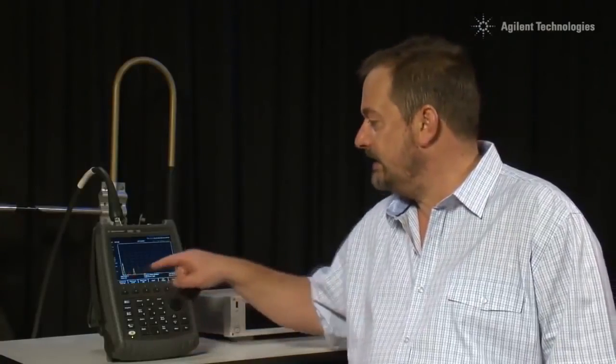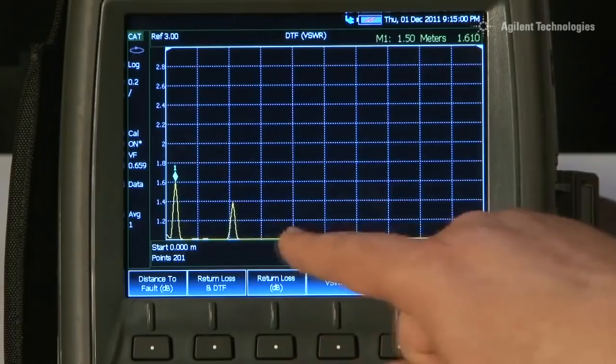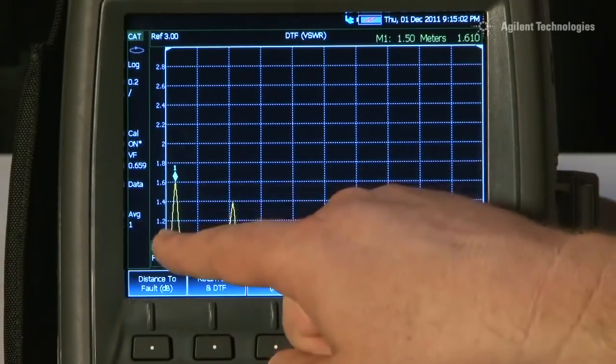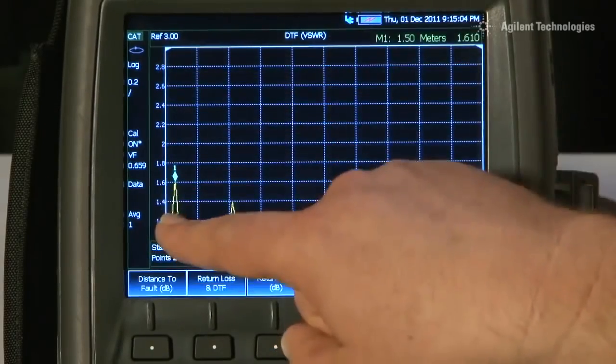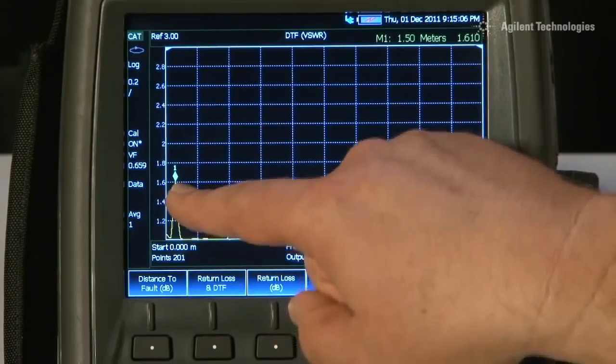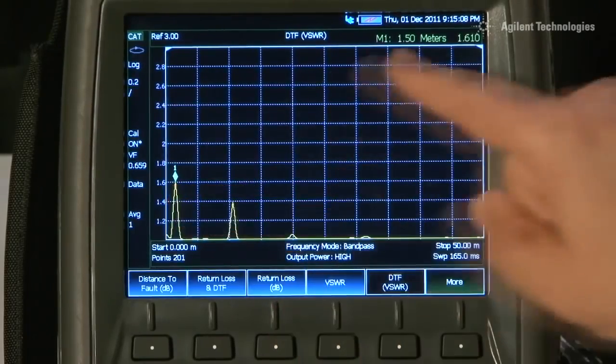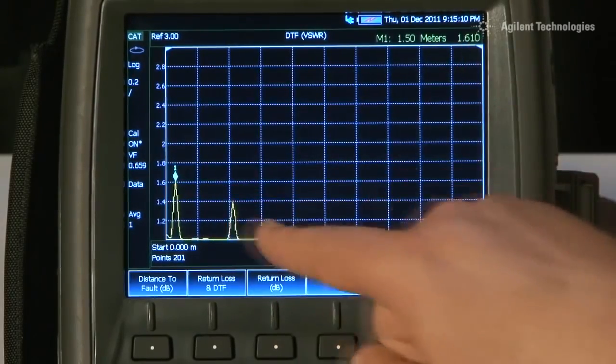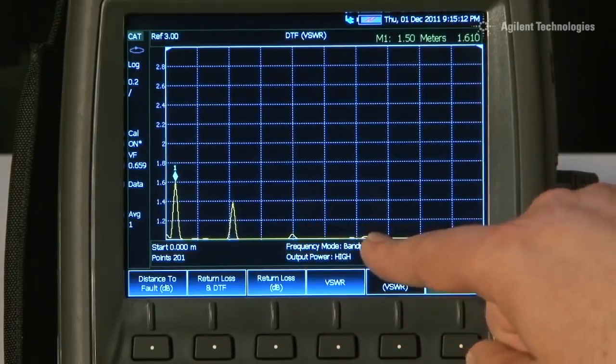Now you can see exactly the same trace with the four peaks but now with a scale on the Y axis of VSWR. You can see that even the worst peak here has a VSWR of about 1.6 and the other peaks are below 1.5, which may be acceptable for your installation.